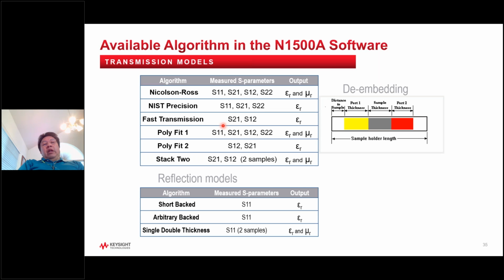And unfortunately, we cannot measure a layer. Because the measurement uses S parameters, it only gives you one S parameter, so we can only calculate a composite of the whole material together. We cannot separate out the layers. So if you want to measure that thin, I would suggest two ways.